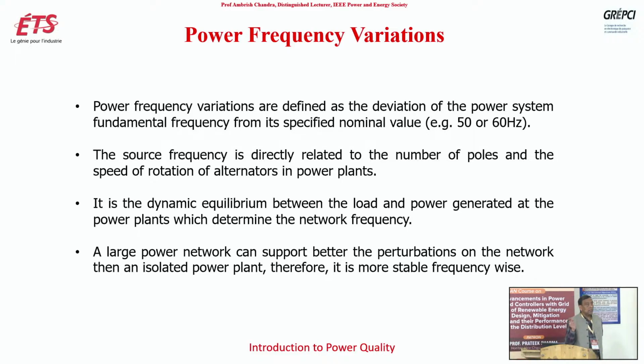But if there is a sudden, big change on the load, and if load is increased too much, then it will generate the currents which are flowing in the stator winding, and a large electromagnetic torque is generated, which will be a braking effect on the rotation of the rotor. And in the meantime the governor takes effect, flowing more water, so that the speed remains constant. So this is basically it.